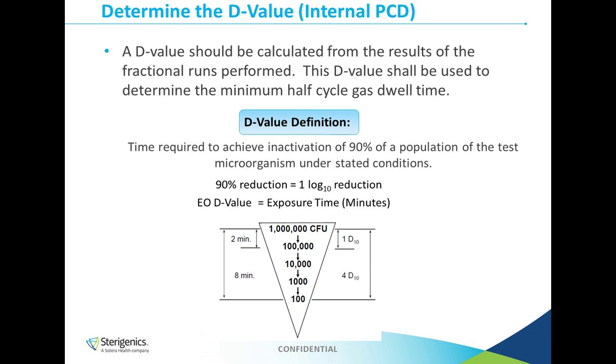Or in other words, the amount of time it takes to reduce that BI population by 1 log. So if you use a 10 to the 6 BI, going from 1 million CFUs down to 100,000 CFUs, the time it takes to reduce it by that 1 log would be your D value. Now in the definition, it's important to note that it says under stated conditions. That is, as those conditions change, that D value is going to fluctuate.